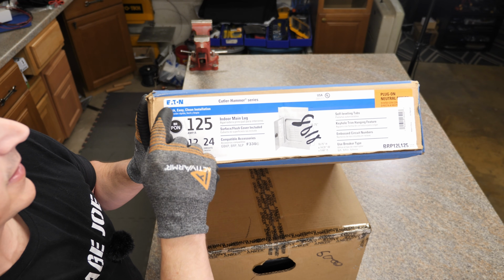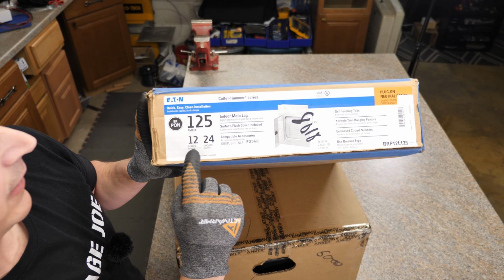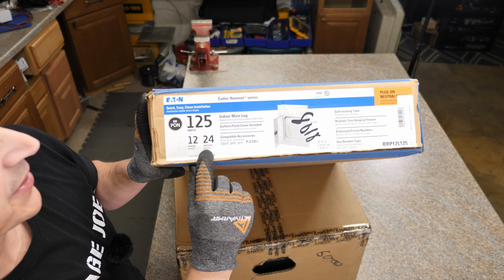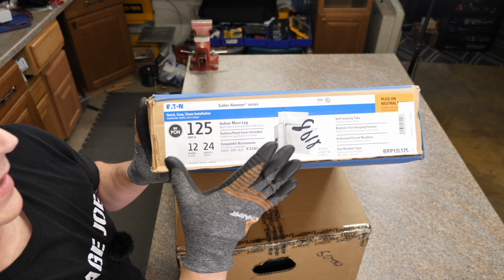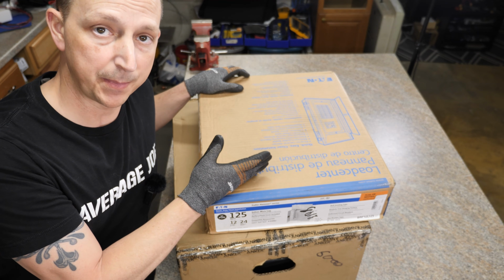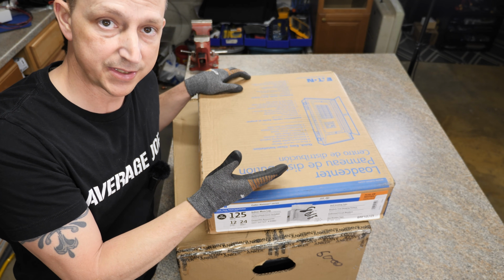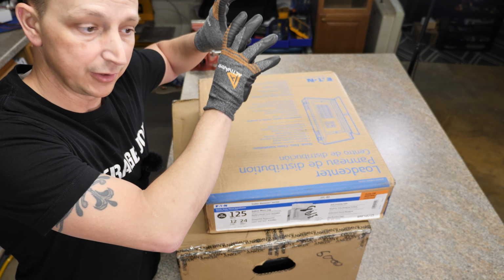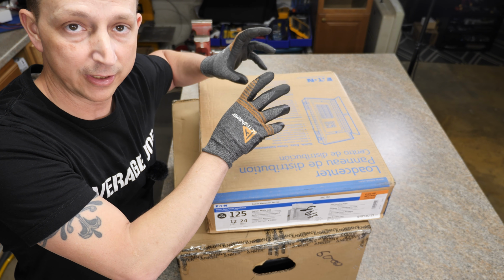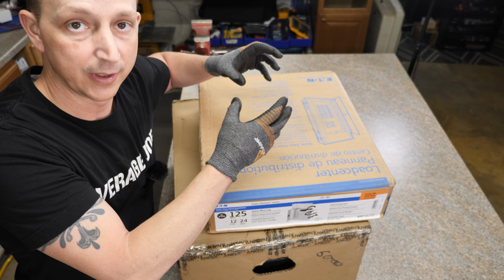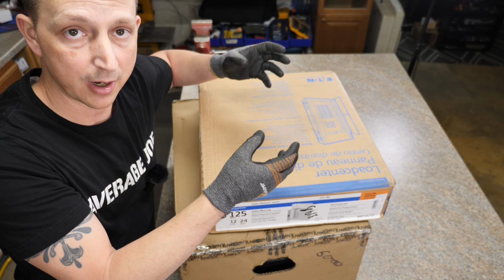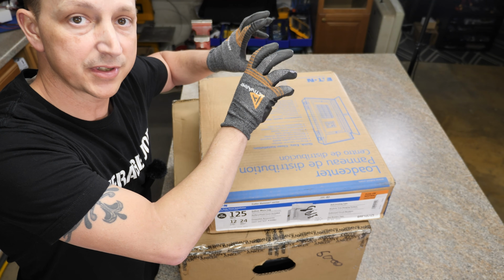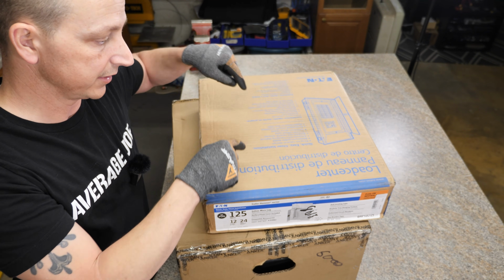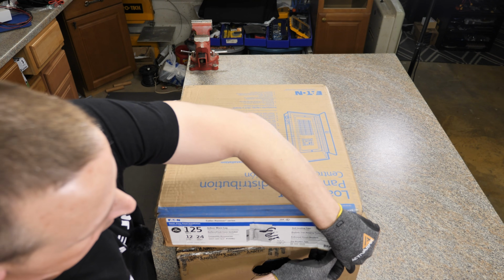So what we have here is an Eaton 125 amp, 12 space or 24 circuit indoor main lug panel. Basically this is the sub panel you'd install in your house, and you'd choose circuits off your main panel—your critical load items, or stuff you'd want during a grid failure or to start your off-grid journey. You'd select those 12 circuits and move them over to this panel.